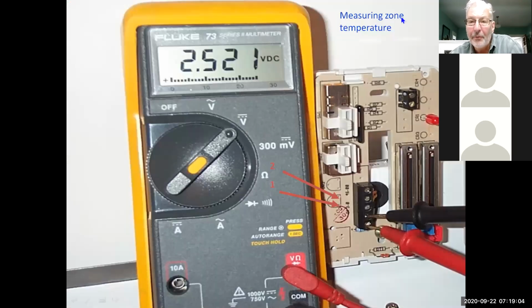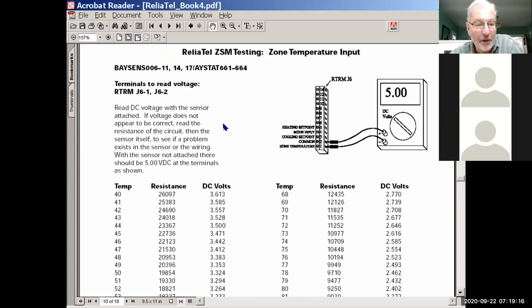If I measure the actual zone temperature, and again, that's terminal 1 and 2, and I read 2.52 volts on the zone temperature, if I go to the zone temperature chart, 2.52 is roughly 76 degrees is the actual space temperature. So if you read the DC volts or the resistance value, you should be very close to this. If that space was 68 degrees and it was telling us it was 76, well, then we know we have a bad control. We need to replace that control.